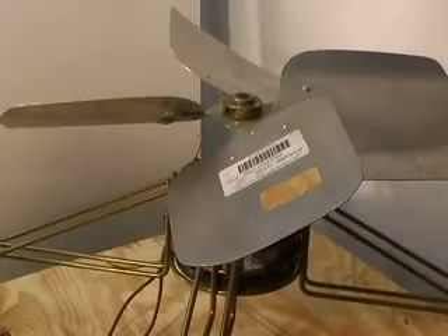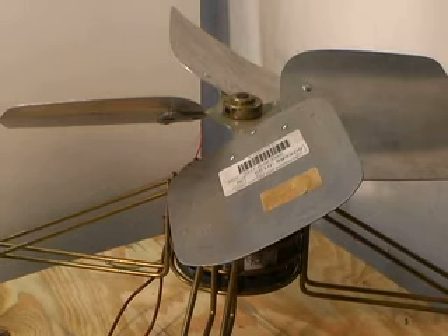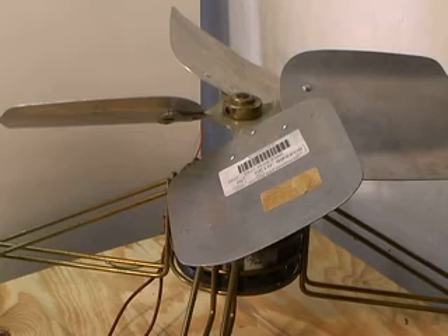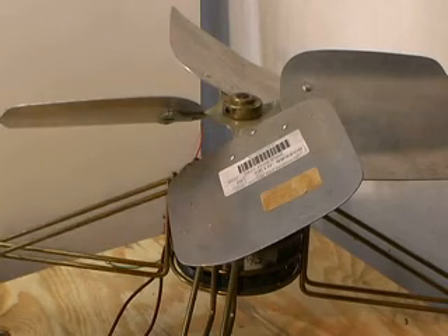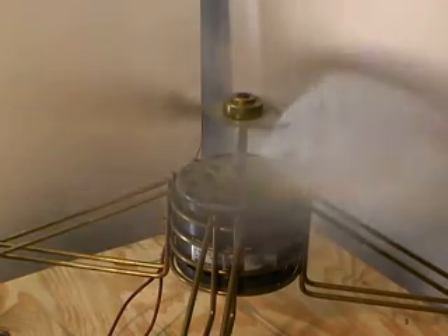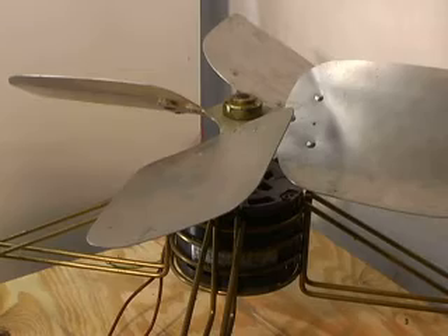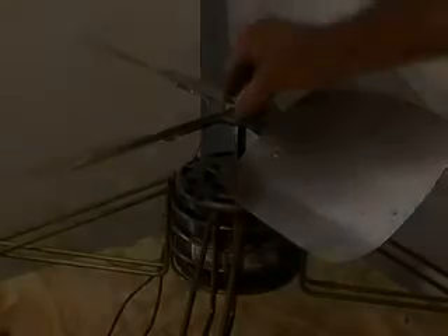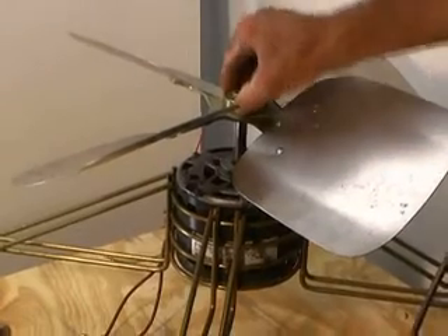Okay, now I've got an old motor that I took off of a heat pump sometime back, which was a bad motor, and I'm going to start it up and listen to the difference in the sounds. You could hear an obvious abnormal noise when it started up, and then when it got to running, there's a little whine. I don't know if you can pick it up with this little microphone. But on this particular motor, I can show you the main thing that's wrong with it, which is the bearings wore out. That slack in the shaft, side to side slack, that's always a no-no.